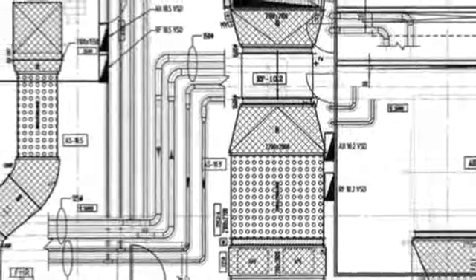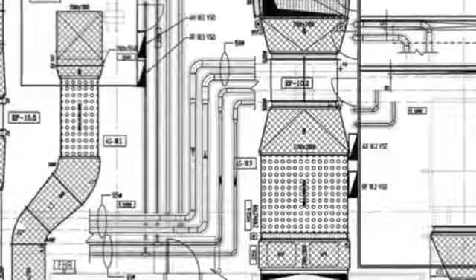Back in 2011, Bob asked me to audit the entire Harrison campus of Boston Medical Center to develop energy conservation measures that would reduce their operating costs but also improve aging infrastructure. Through auditing the building, we realized that this building had eight 50,000 CFM air handling units with a total air handling capacity of 400,000 CFM for 200,000 square feet.